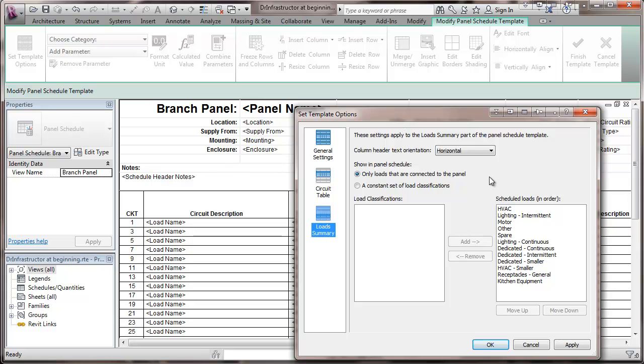Which means that if you only have, say, lighting loads, all it's going to show is lighting in that summary. On the other hand, a consistent set of load classifications means that you have exactly the same classifications for all your panels.